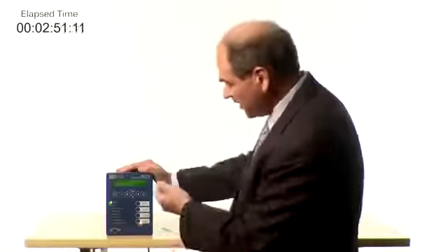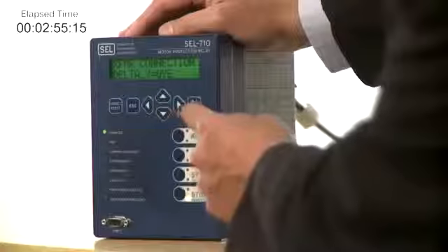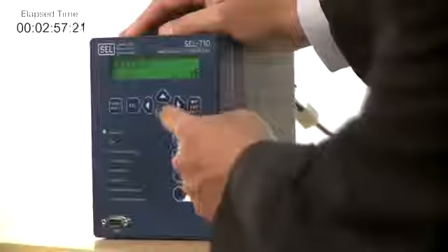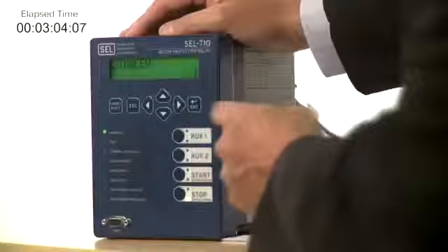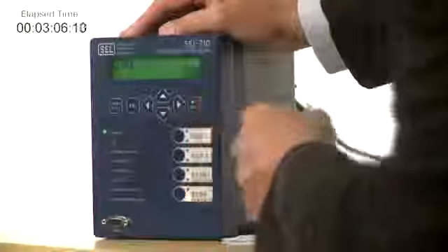And we have a Y connection for our motor, so I'm going to change the delta Y setting to Y. This also has an option for a single voltage, but we have 3 voltages, so we leave the single voltage set at no. So now we're back to where we started on the CT ratio.